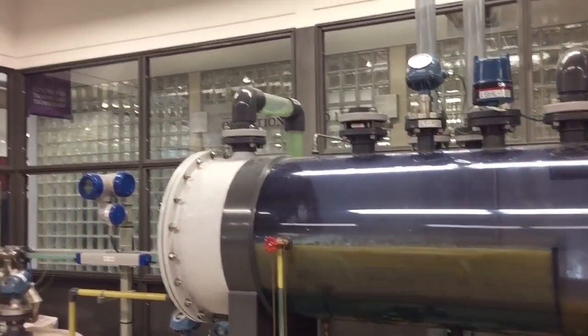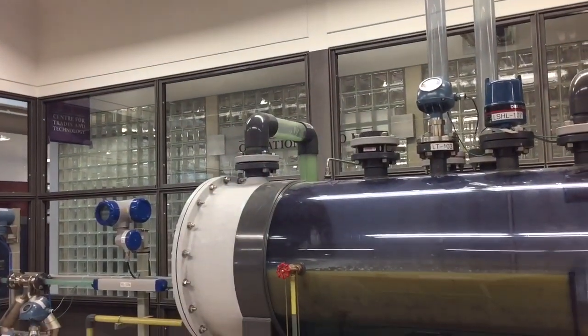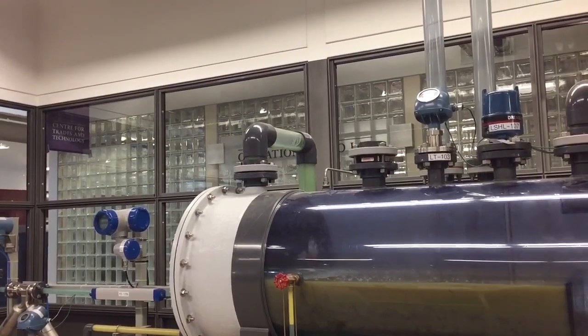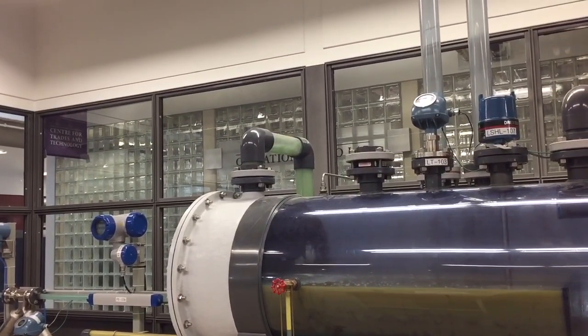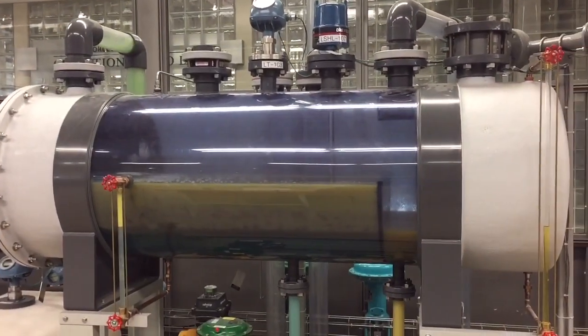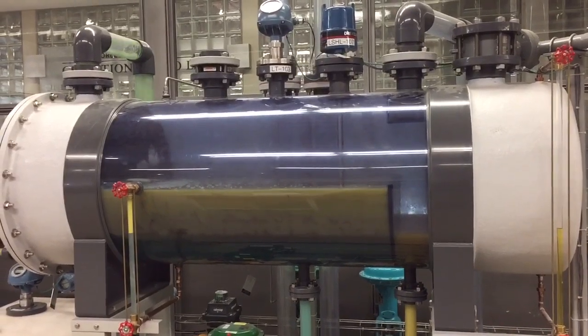So with the proper flow into the vessel there, we have about what would be probably 3 to 1, 4 to 1 ratio of water to oil right now. It seems to be controlling quite good. So after our step change is done here we'll check to see how it did.